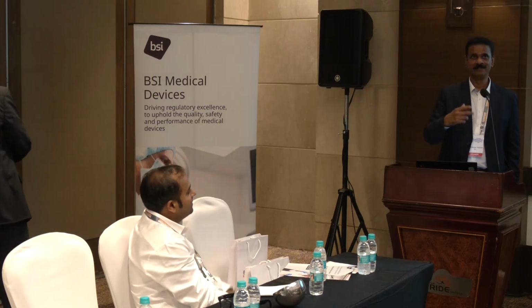Again, in the coming slides, I will explain what it is. Manufacturers claim we are following the equivalency route, but when we review, it is not an equivalent device. It is a similar device, which is not acceptable. That is what comes up. Everything they dump into the CER, so the reviewer is not clear which route you want to do. Because, as I said in the morning, we need to follow your audit trail, and in that audit trail we need to see that. As the presentation progresses, you will get more clarity. So what we will expect, and why the route to compliance is important.